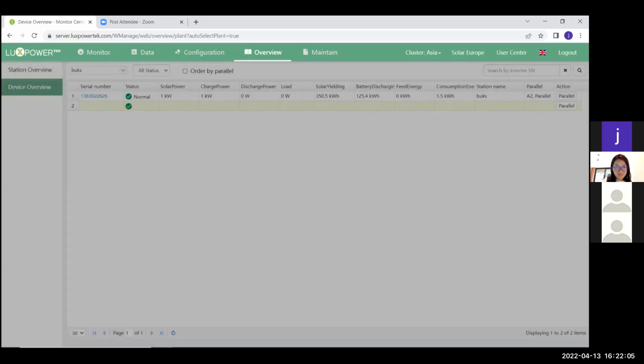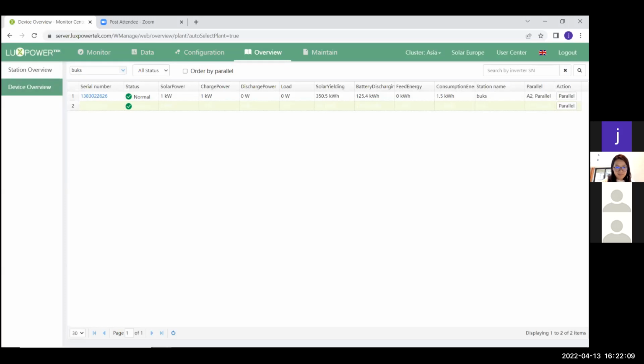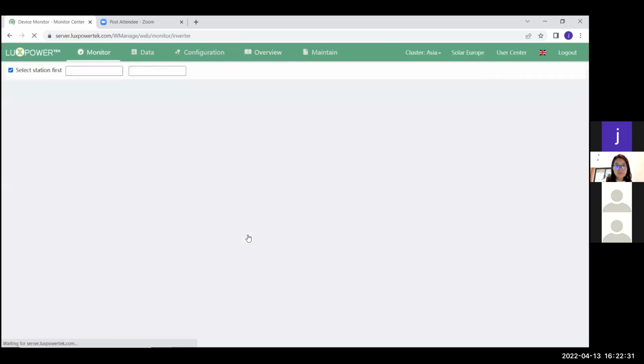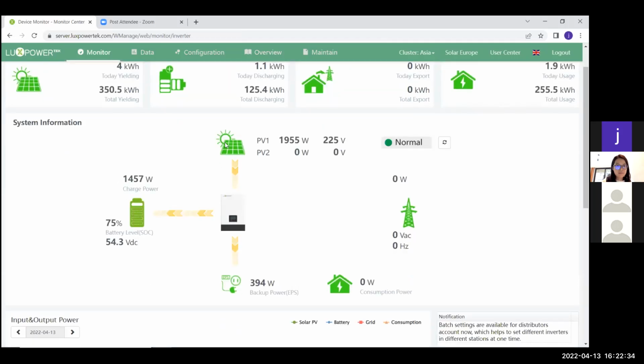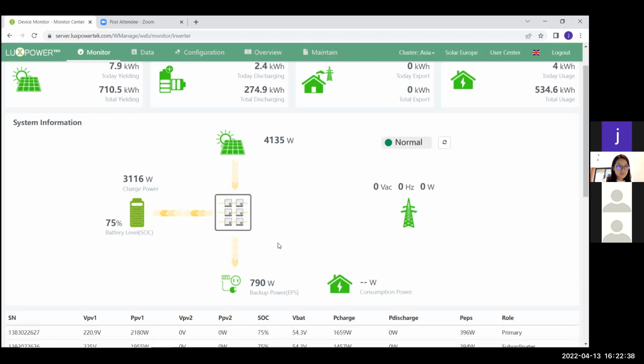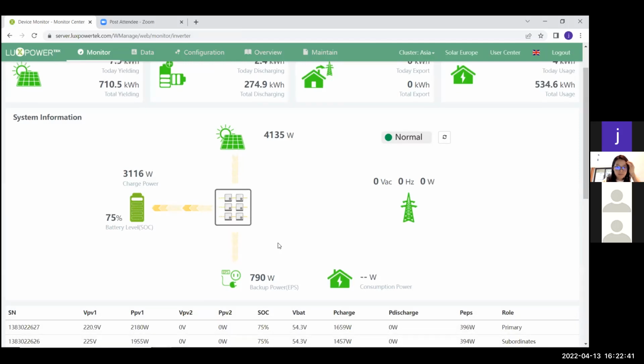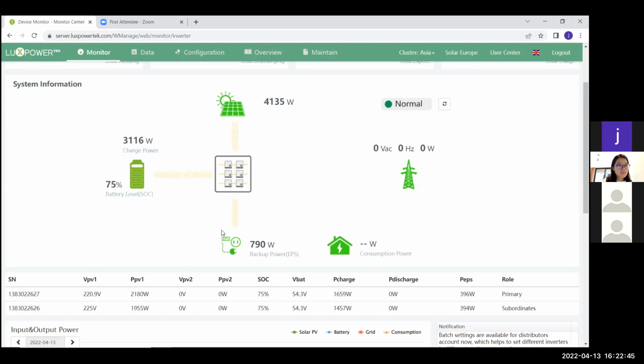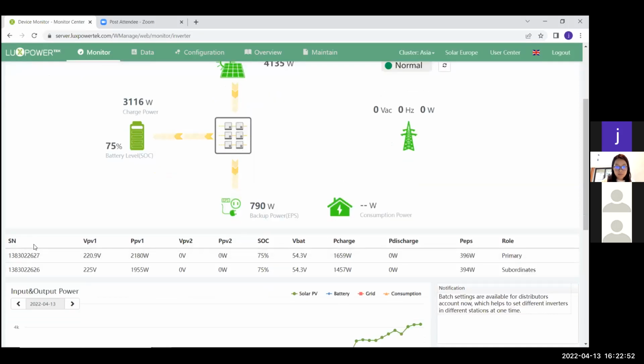But always try to make your master inverter your number 1, 2, 3, 4, 5 on the paralleling while it's on the app. Now, the paralleling on the app has nothing to do with the physical settings on the machine for doing it while in parallel. It's only for the monitoring, to put all your information on one monitoring page so that you can see all the information of these inverters in one complete block like this. So that's basically for adding a station, adding your data loggers to the station, and having the capability to monitor a parallel system as well as a system that has only one unit in it at one monitoring page. In a parallel system, you'll see all your inverters' numbers will go down depending on how many you have.